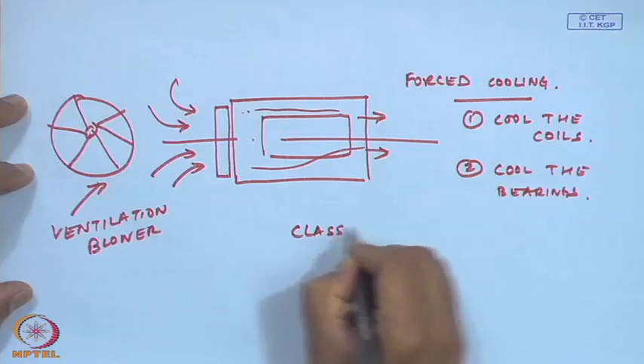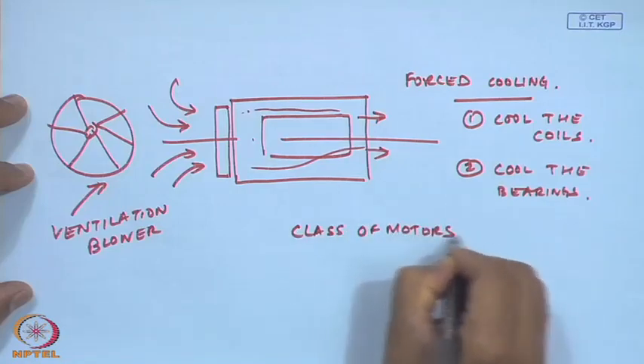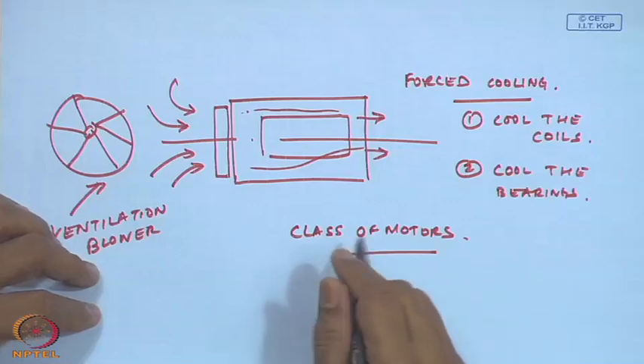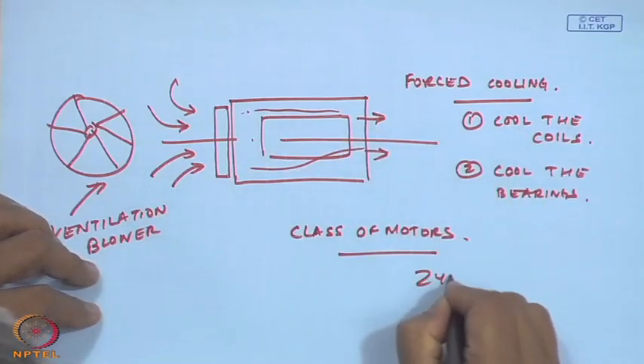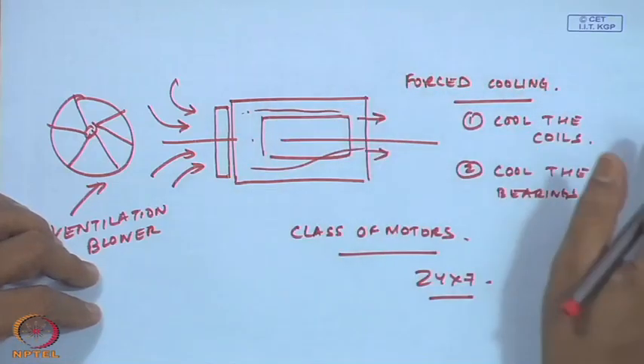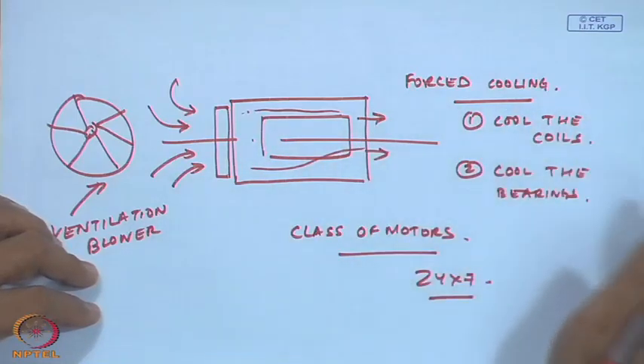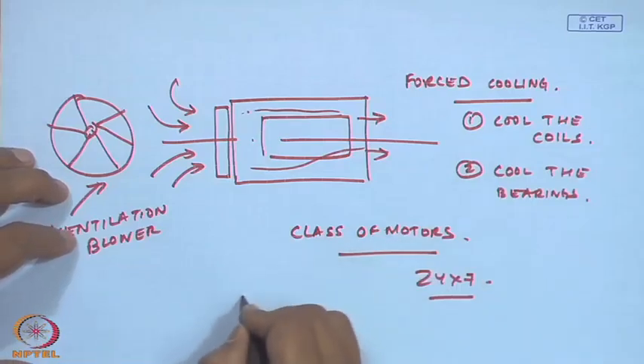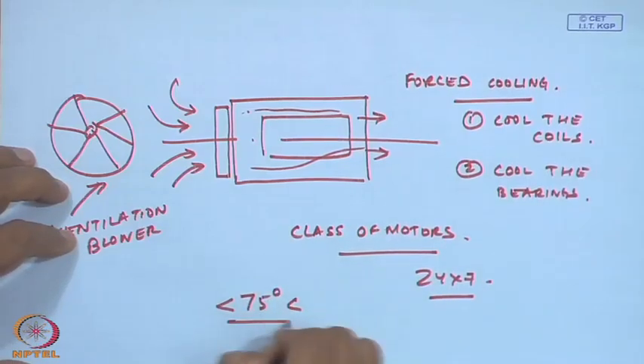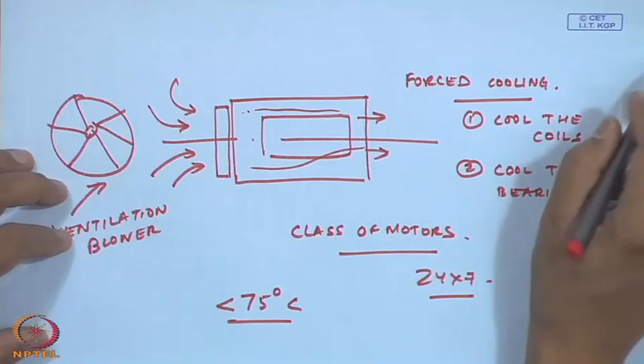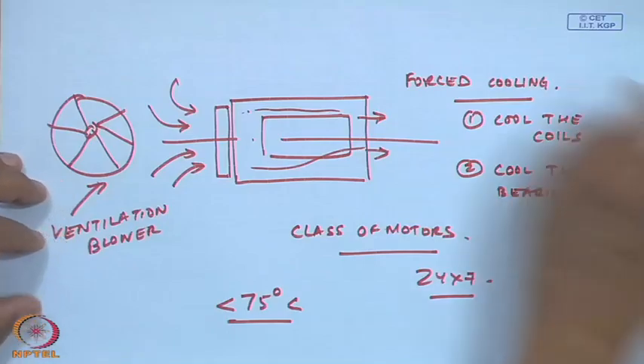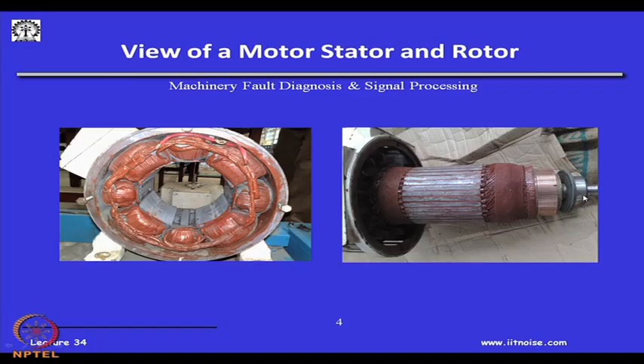There are a class of motors which run continuously round the clock, 24/7, in a plant. They take breaks only for maintenance, otherwise they run continuously. There are also motors which run for short spans. You can imagine that if this heat is not dissipated, the temperature is going to build up. Typically, the bearings are maintained on the safe side, around 75 degrees Celsius. And in some special motors, there are alarms which let you know if the bearing temperature is increasing, and either the motor shuts down or we have to have an extra cooling unit to cool the motors.